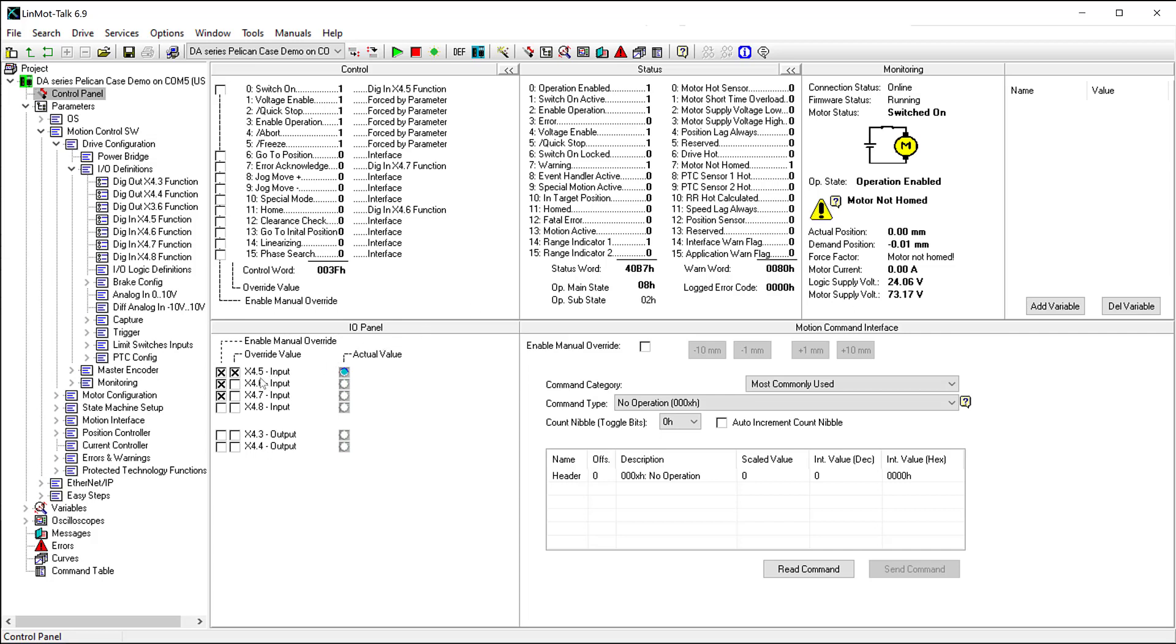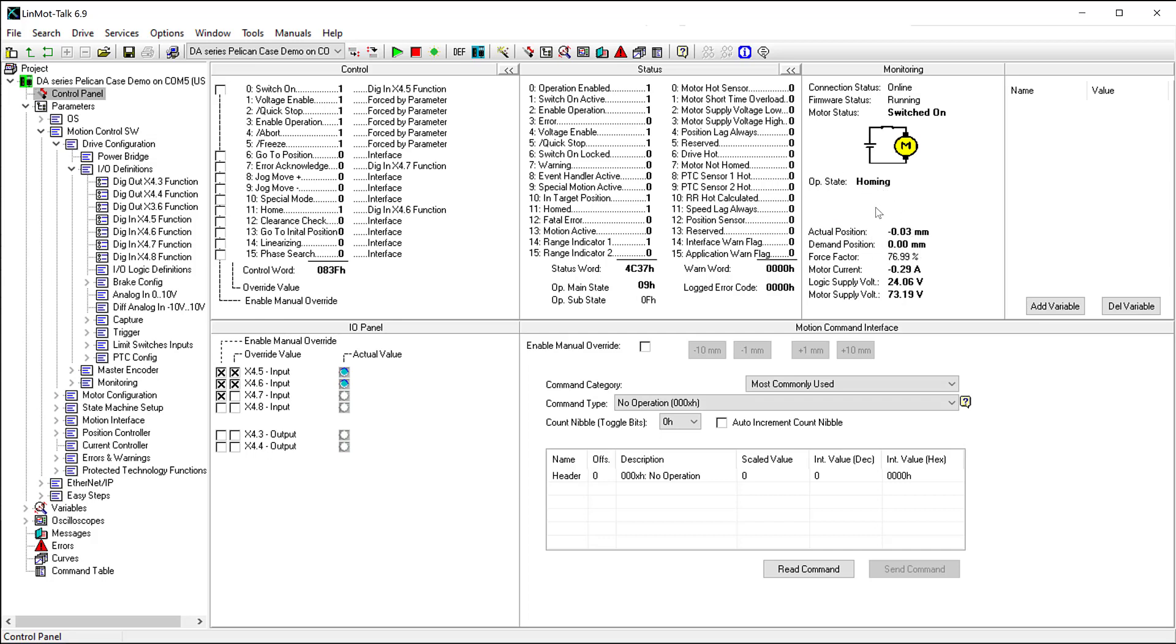If we toggle X4.6, we can see that the home bit in the control word goes high, and the motor begins its homing procedure. Once the motor is homed, and the home bit in the control word goes low, the operational state says, operation enabled.